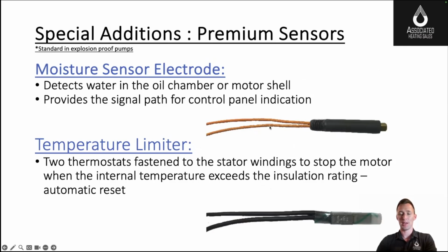The top one here detects water in the seal chamber or the motor shell and will alarm the panel. At that point, maintenance personnel could pull the pump, maybe take it to a motor shop and have it rebuilt, resealed with new O-rings, new seals, and you would have saved an expensive pump. This would be the idea, saving a really expensive double seal pump before it burns up.